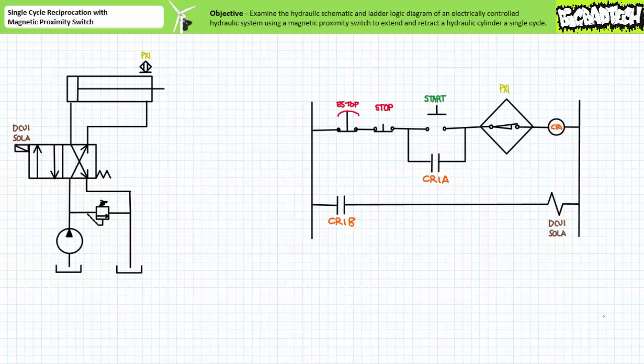Good day and welcome to Big Bad Tech. I'm instructor Jim Pytel and this is a short application example of an electrically controlled hydraulic system. Our objective is to examine both the hydraulic schematic and ladder logic diagram to predict the behavior of an electrically controlled hydraulic system using both operator initiated manual input and automatic mechanical input — in this case a magnetic proximity switch to extend and retract a hydraulic cylinder a single cycle.